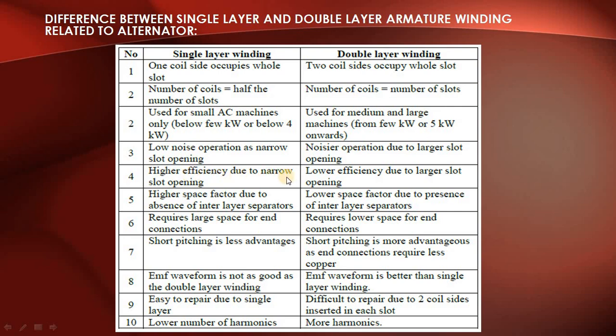Fifth difference: single layer has higher efficiency due to narrow slot opening; double layer has lower efficiency due to larger slot opening. Sixth difference: single layer has higher space factor due to absence of an interlayer separator; double layer has lower space factor. Seventh difference: single layer requires larger space for end connections; double layer requires lower space for end connections. Short pitching is less advantageous in single layer, but more advantageous in double layer as end connections require less copper.